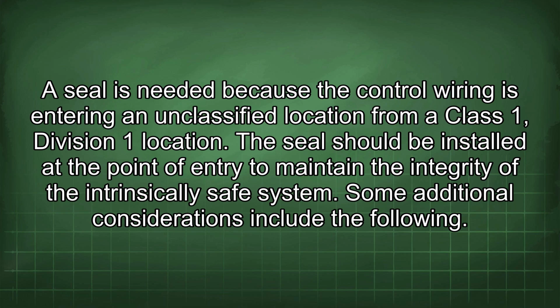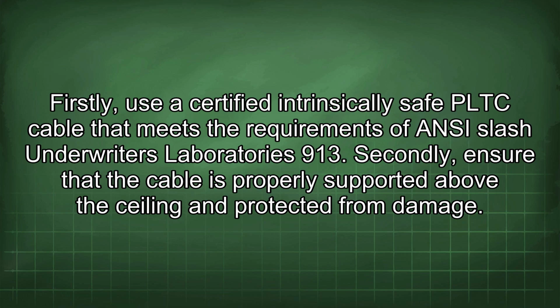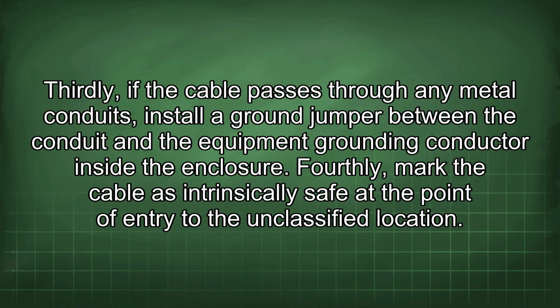Some additional considerations include the following. Firstly, use a certified intrinsically safe PLTC cable that meets the requirements of ANSI/Underwriters Laboratories 913. Secondly, ensure that the cable is properly supported above the ceiling and protected from damage. Thirdly, if the cable passes through any metal conduits, install a ground jumper between the conduit and the equipment grounding conductor inside the enclosure. Fourthly, mark the cable as intrinsically safe at the point of entry to the unclassified location.